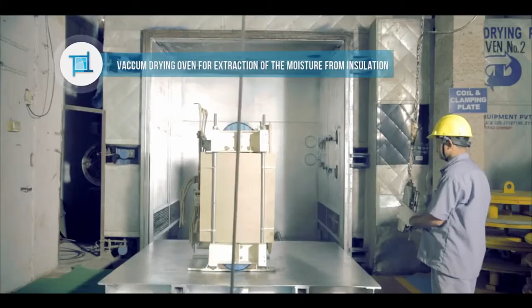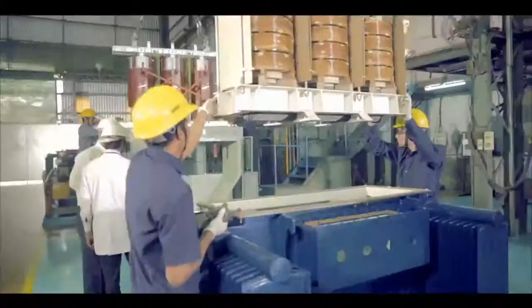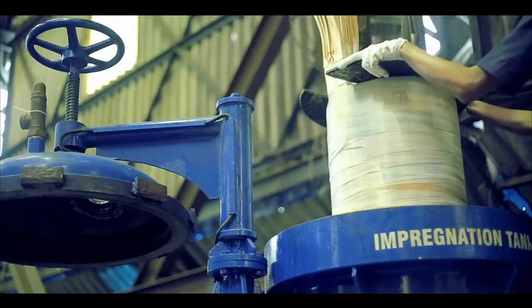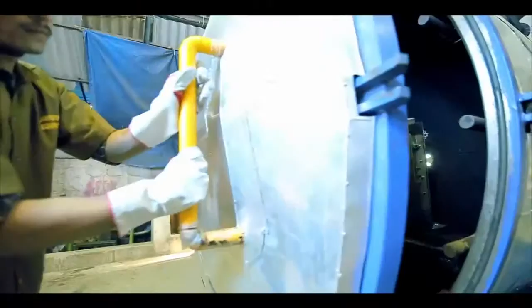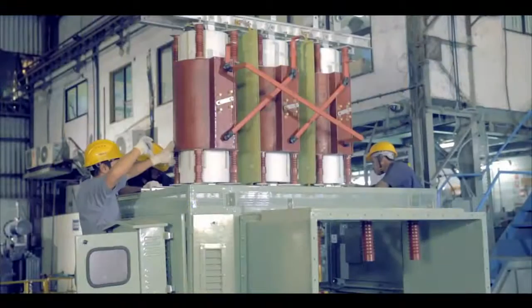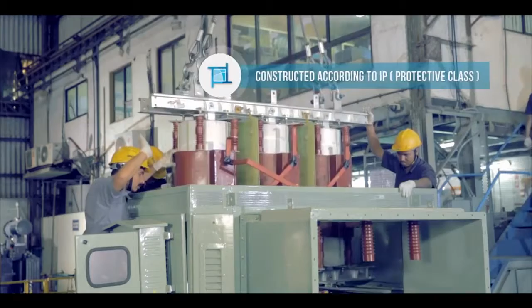The entire core coil assembly of oil-cooled transformer is kept in a vacuum drying oven for extraction of the moisture from insulation, after which it is placed in a tank. For dry-type VPI transformers, each coil is vacuum impregnated with drying process, and cast resin coils are capsuled with resin in vacuum chamber. Then, core coil assembly of dry type is placed in enclosure, which are constructed according to IP or protective class as required.